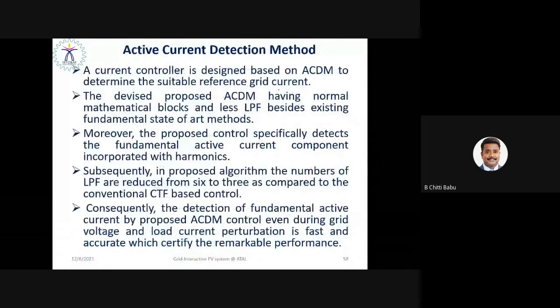Yes, and here, as I mentioned, this is an active current detection method for generating the reference current. It has a very simple mathematical block, with fewer low pass filters compared to the existing state of the art. Moreover, it detects the fundamental active current component in the presence of harmonics. Subsequently, it reduces the number of low pass filters from 6 to 3, so it can be easily implemented even in a DSP, the TMS320F2812 processor. Consequently, the detection of the fundamental active current by the proposed ACDM control, even during grid voltage and load current perturbation, is fast and accurate, which gives remarkable performance.